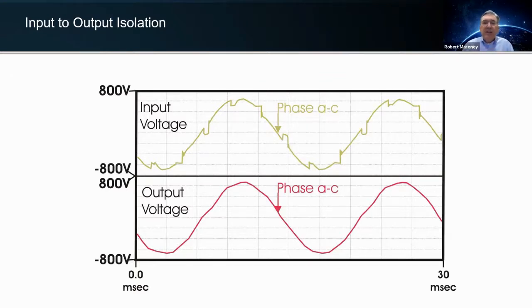Here you can see the output waveform nice and clean, and that goes on for an extended period of time regardless. One of the benefits with the UPS is we don't go to discharge, or we don't go to flywheel or energy storage, until a minimum of 15% deviation from nominal low, 10% high, and until then we can do full correction to tolerance requirements, plus or minus 1% on voltage, okay?